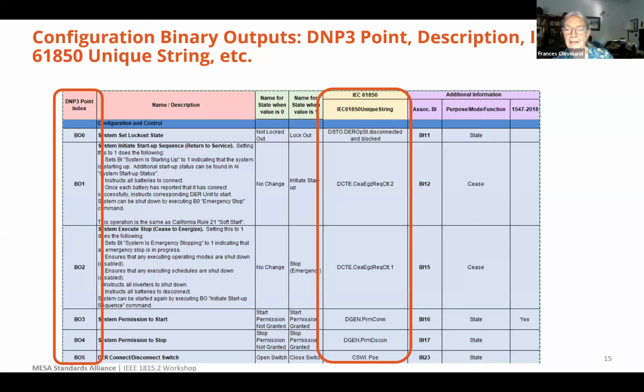The other circled area is the IEC 61850 unique string. We kept the names from 61850, but not the data structure, since that's fairly complex and not directly compatible with DNP3. There is a way to do that, but we decided to go with a straight mapping of the names to the data points. The name in the middle box comes from 61850, and the data point is just the DNP3 data point.